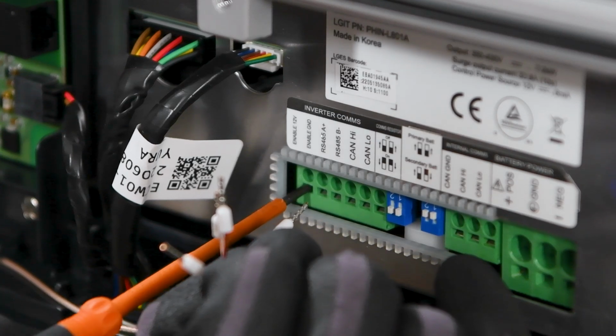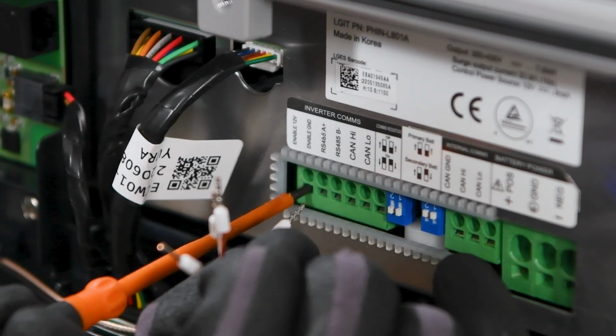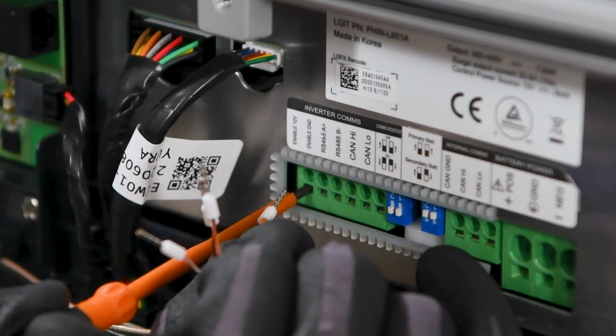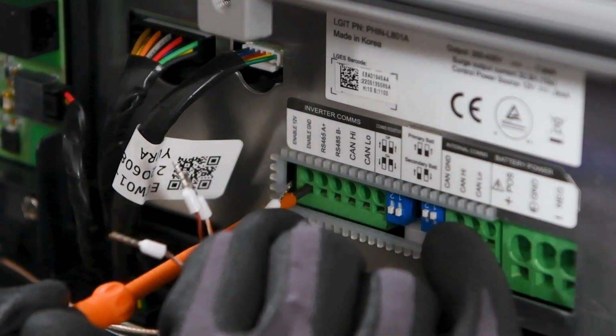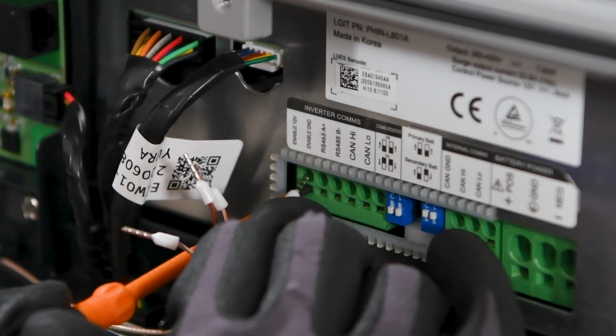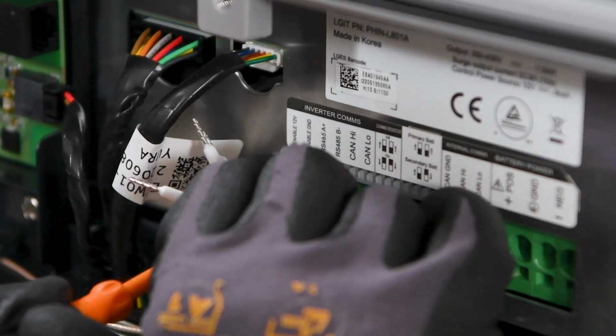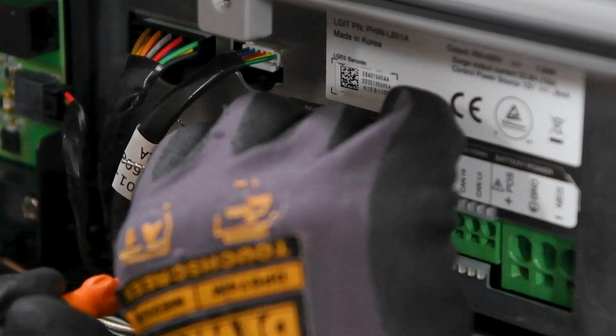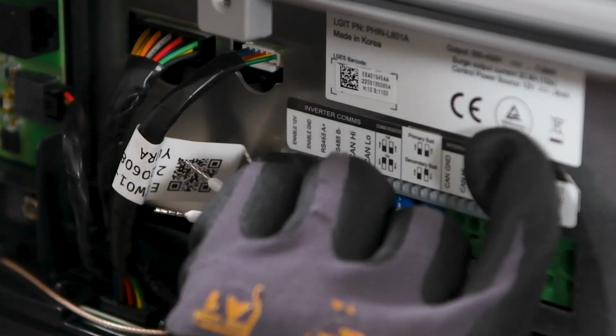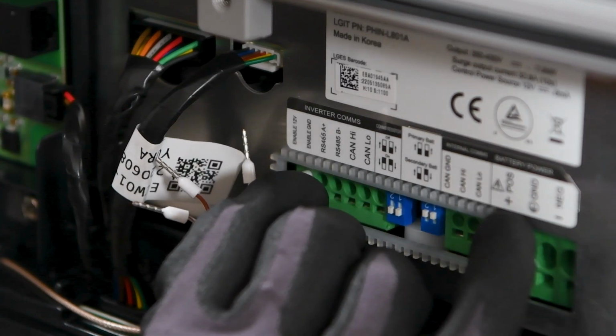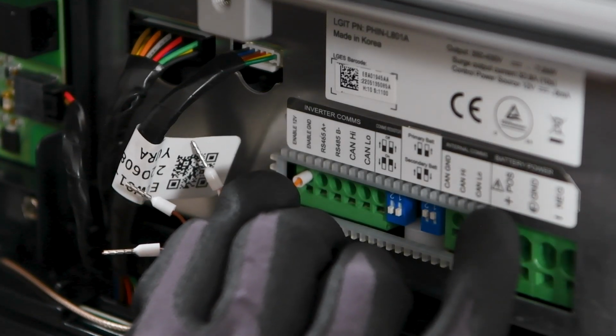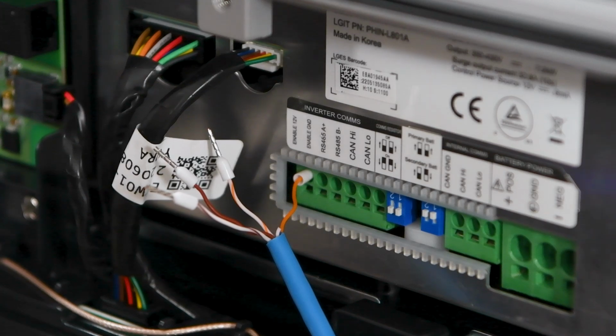If you take a small flat screwdriver, insert it into the small rectangular portion and push slightly, it will open up the portion inside the circular terminal. When you insert your ferrule end and release the screwdriver, the teeth will close down on the ferrule. Give a slight tug to confirm a secure fit.